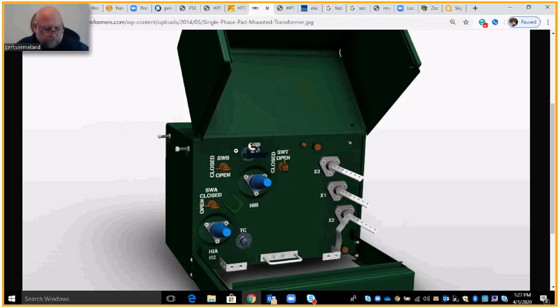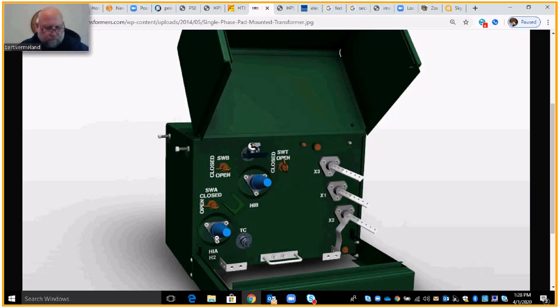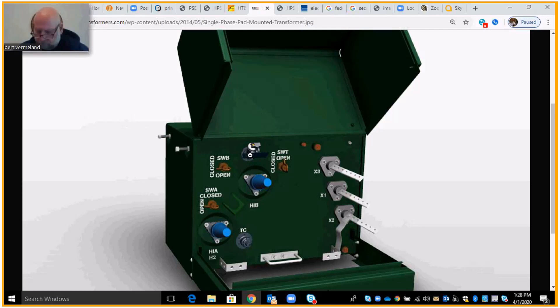There is another bayonet fuse, which acts the same as in the three-phase transformer — it separates the core transformer windings from the primary conductor. Think of it as inbound here, outbound here. Inside the transformer there's a bar between those two points, and off that bar a tap goes to the fuse, then into the windings. If there's a secondary fault or an internal fault in the transformer, that fuse is going to blow. Remove the fuse with the shotgun stick, replace it, reinstall it — there'll be a video showing how to do that.